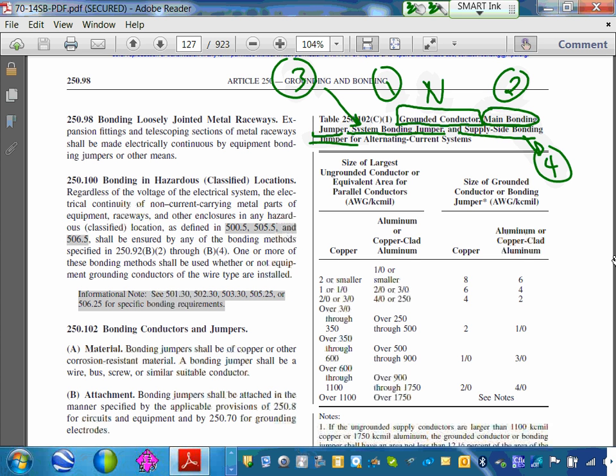Okay, so gentlemen, 4 things coming out of this table. And by the way, this is a brand new table, born in 2014. So this is fresh for you guys. Before that, they used to refer you to 250.66. Now look how this table goes. It goes by the service conductors. So how many runs? How many conduits? 4 conduits. Now we need a neutral in each conduit. So you size the neutral based on the conductor inside this particular conduit, right?